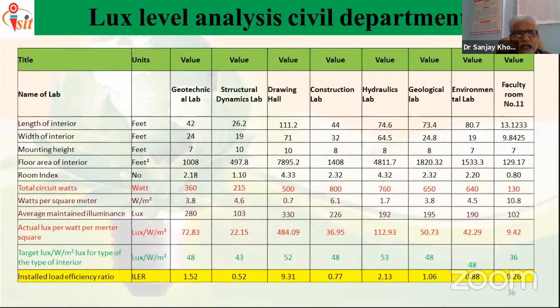If the size increases, the number of points for lux level measurement also increases. So we calculate the room index, whose only significance is determining the number of points where you need to measure lux through the lux meter. Next is total circuit wattage - suppose for this it comes to 360 watts.